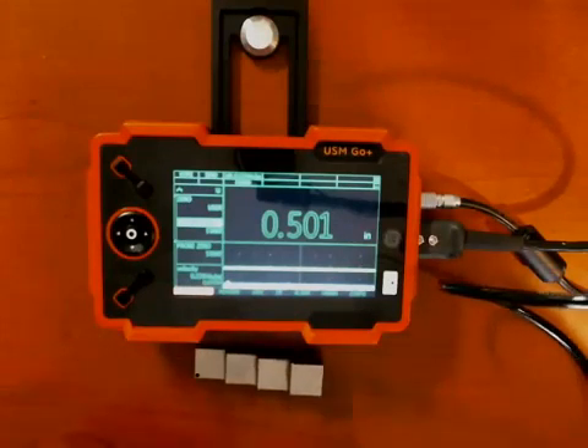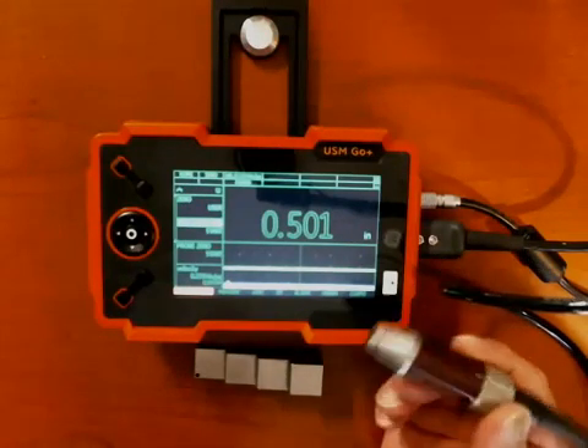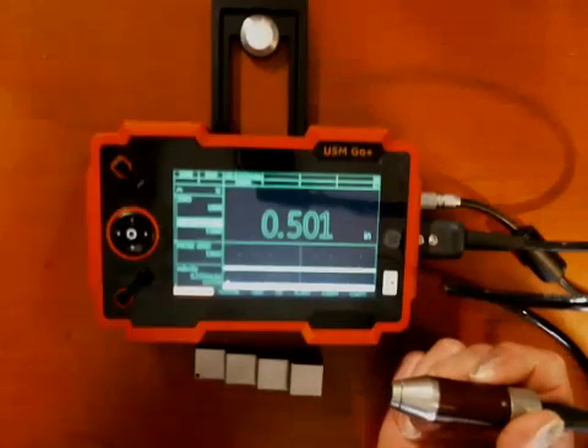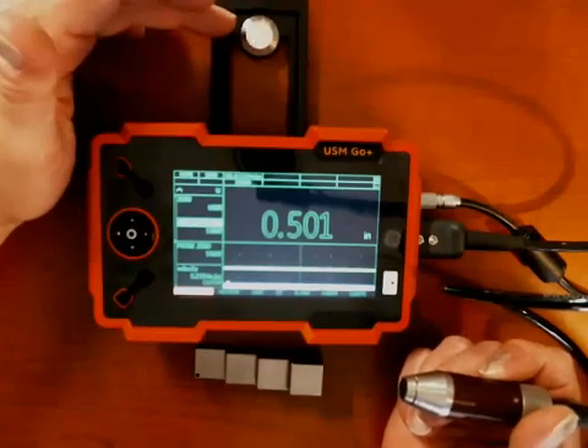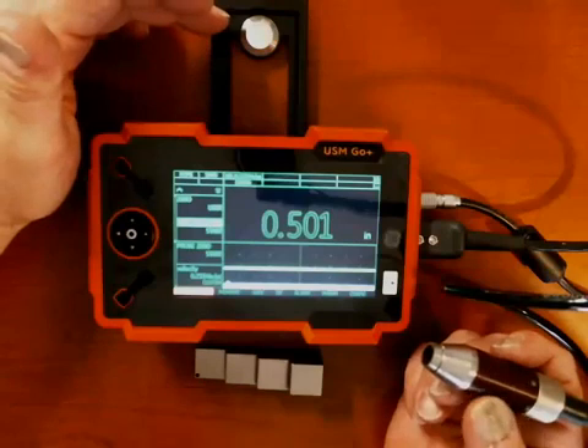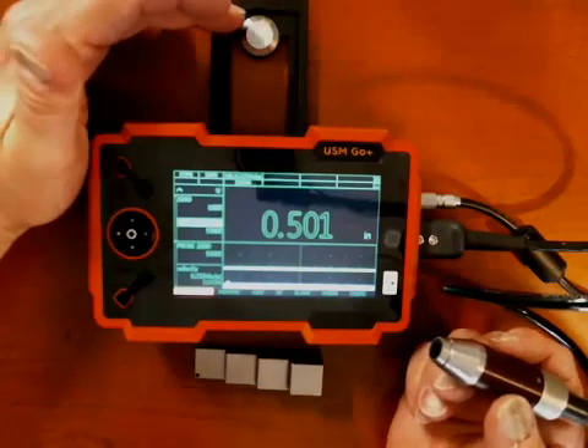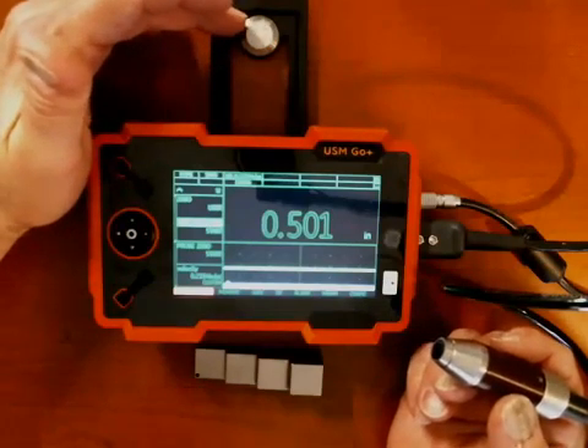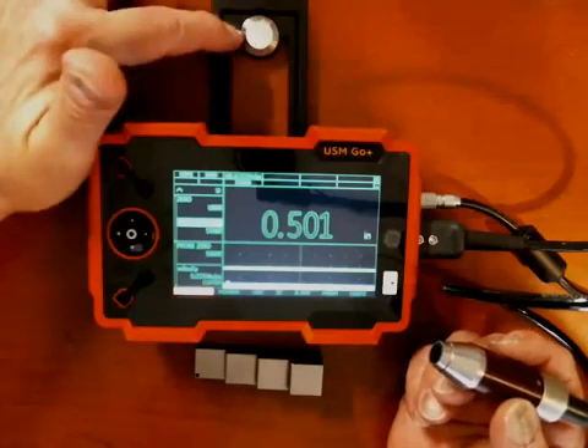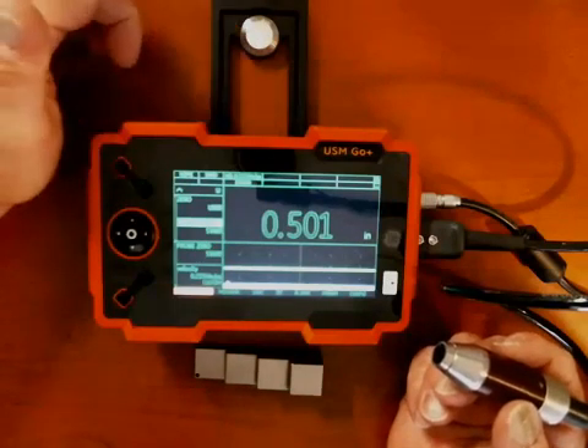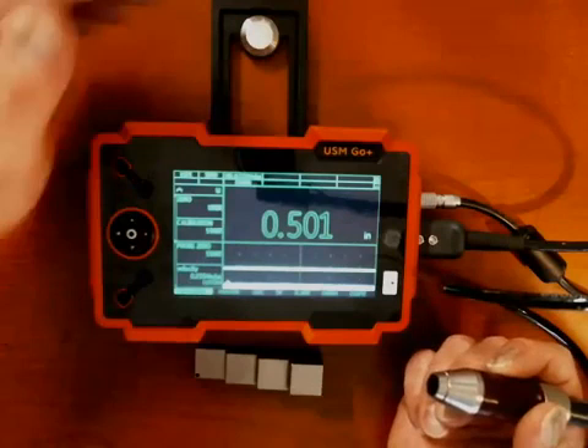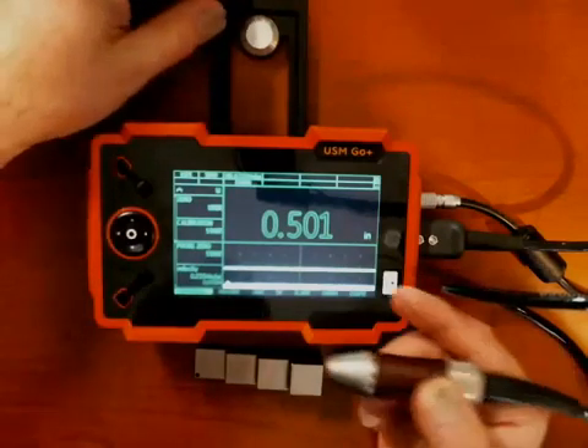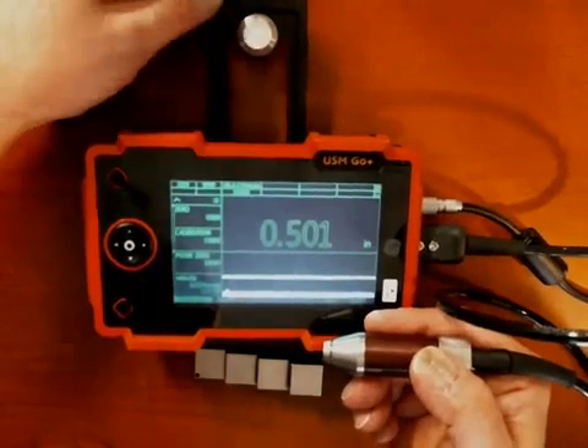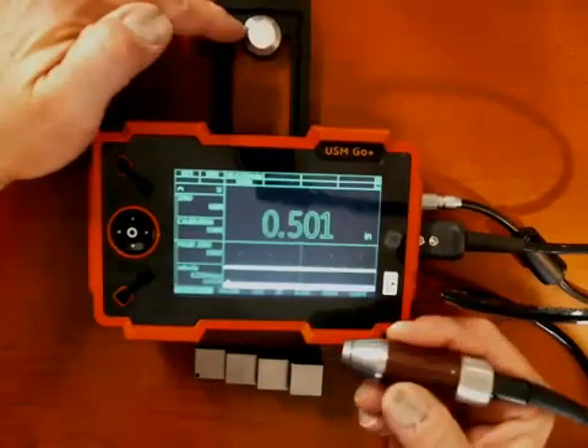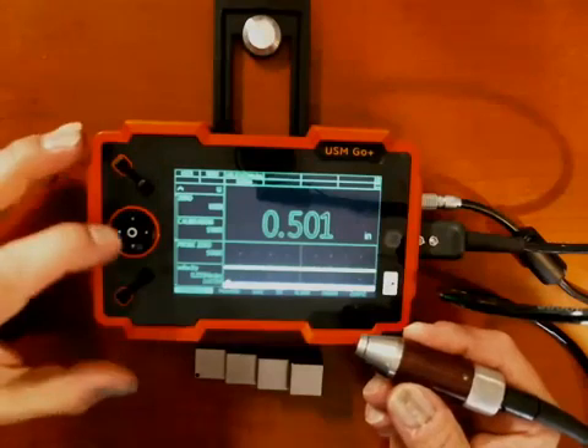Okay. Now, for calibrating the DA590, we actually don't use the zero block, but I want to mention it because some of the probes do make use of this. When you do a manual zero, it will ask you to do things with the zero block, and this is the zero block. It's this button built into the kickstand. Okay, and if we look on the block, there are two numbers engraved on the block. There's a thickness in millimeters and a velocity in meters per second. And it's very important that the instrument knows exactly what those two numbers are.